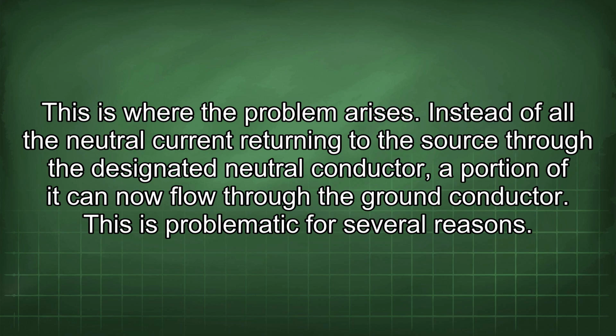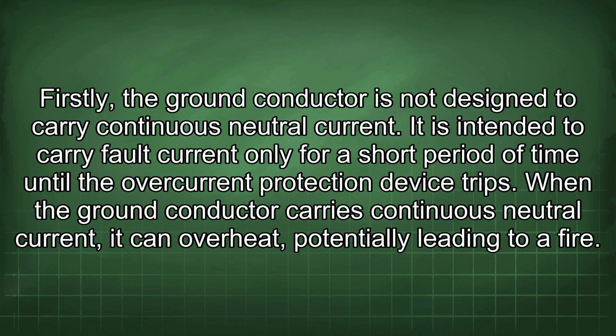Instead of all the neutral current returning to the source through the designated neutral conductor, a portion of it can now flow through the ground conductor. This is problematic for several reasons. Firstly, the ground conductor is not designed to carry continuous neutral current. It is intended to carry fault current only for a short period of time until the overcurrent protection device trips. When the ground conductor carries continuous neutral current, it can overheat, potentially leading to a fire.